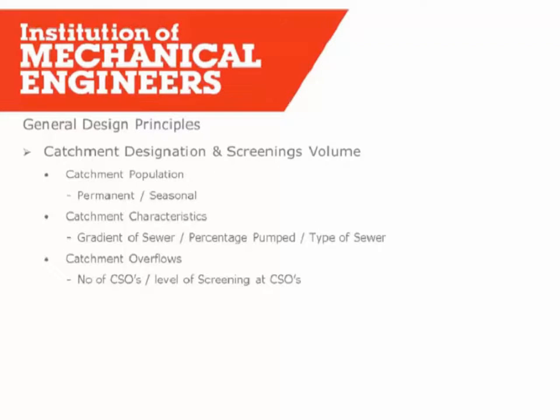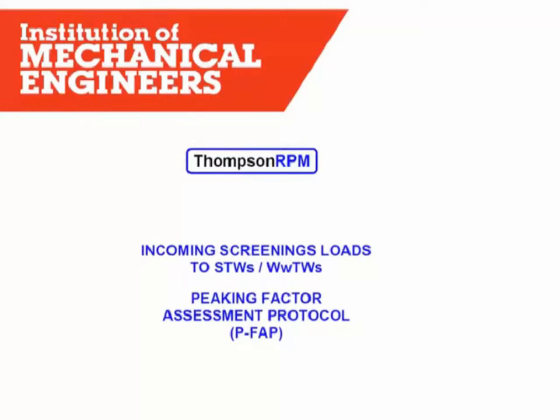Catchment overflows are also important. As water companies have endeavoured to treat combined sewer overflows better, there's now a level of screening provided at most CSOs. Those screens retain screenings in the ongoing flow, so you're changing the ratio of screenings to water that's going to arrive at your treatment works. A way of assessing this was developed by Thompson RPM - the peaking factor assessment protocol. All of those factors are given a peaking factor, and you multiply that by your base load of screenings in the catchment to derive the actual amount of screenings entering a treatment works.